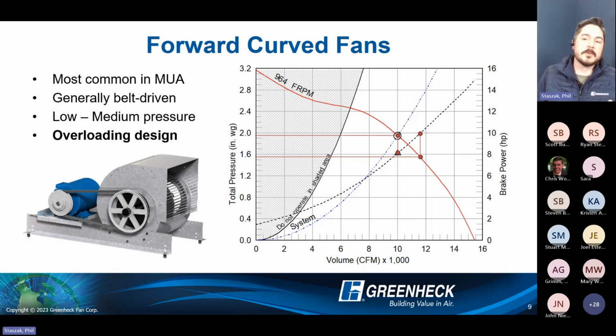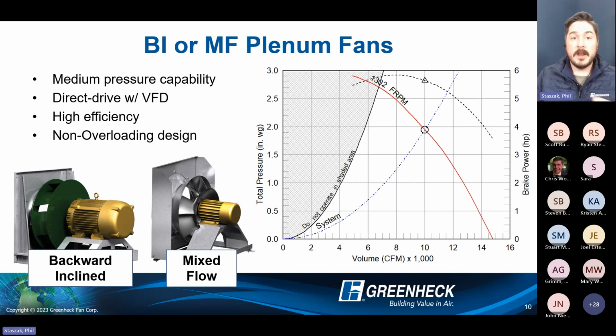This is where VFDs really become crucial to be able to just dial in an air balance with just simple parameter changes rather than changing out belts and sheaves. But again, it's just trying to understand that sometimes with static pressure, we're over designing or over calculating for some of these systems. Now, the benefit of moving to a BI or an MF mixed flow plenum style wheel is that same design now at 10,000 CFM, just under 2 inches of total static pressure.